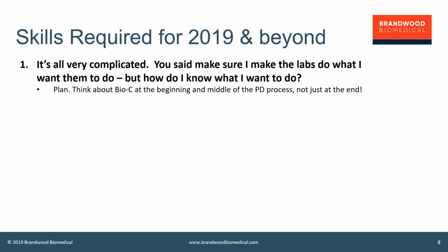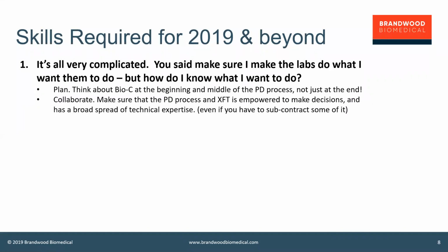You have to think about biocompatibility at the beginning and in the middle of the product development process. You don't just think about it at the end. It's not a validation exercise. You don't just do the biocompatibility testing at the end of your program and say, well, thank goodness that worked. You've actually got to think about this right at the beginning of your PD process. So you've got to have a good plan. Biocompatibility is a design input. Yes, it certainly is. And indeed, how you evaluate for biocompatibility should also be a design input.